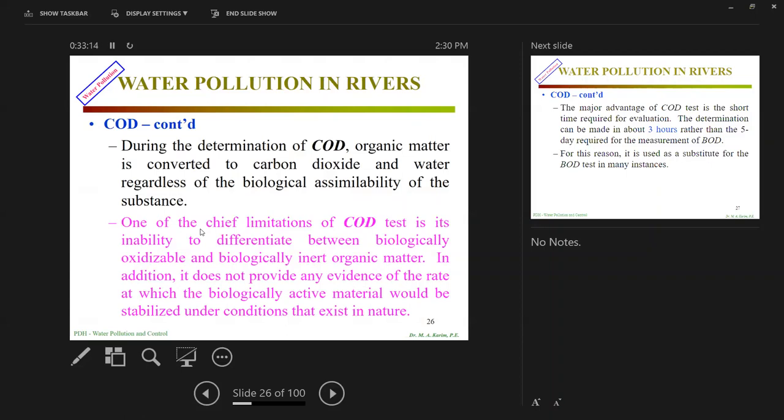It's not just one. There are some advantages and disadvantages of COD and also BOD. In case BOD is not possible, especially with toxic industrial waste, we do COD. If we have any industrial waste with very low pH, or very high pH, or some toxicity, then we cannot do BOD because the microorganisms are dying. So no BOD can be done. In this case, COD is definitely the best option. But there are some relationships between BOD and COD. COD is usually greater than or equal to BOD.